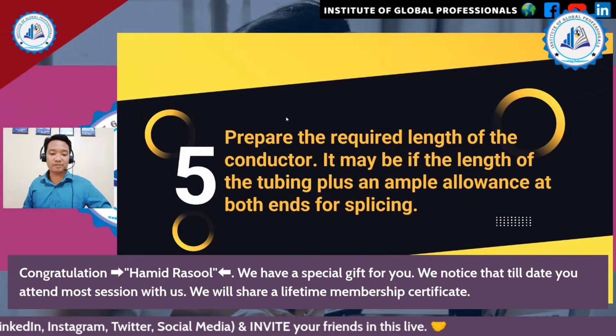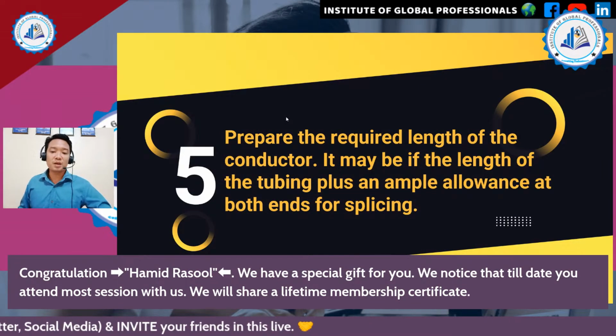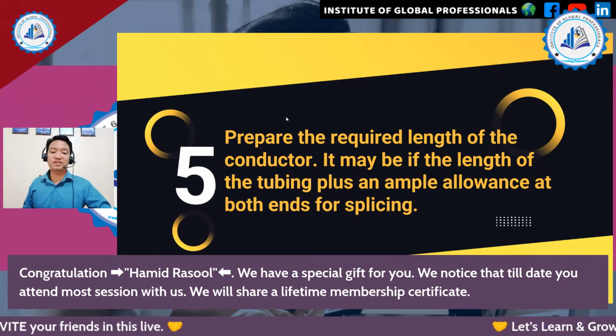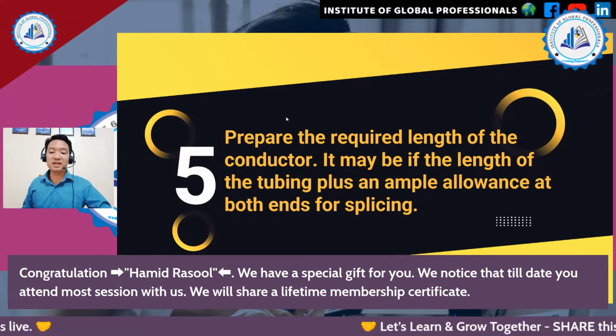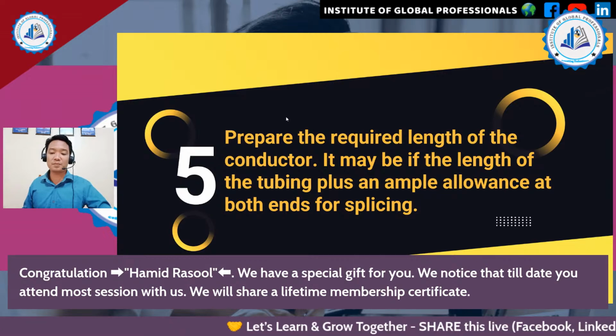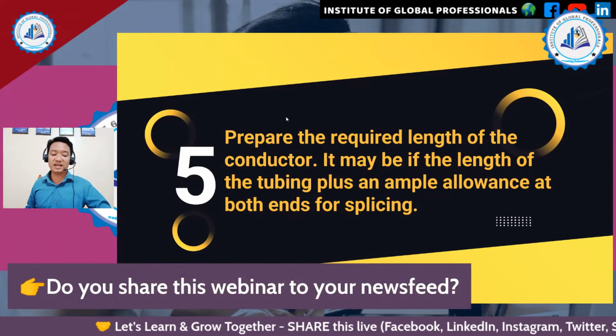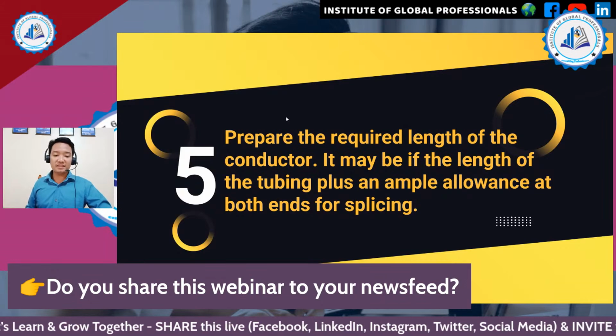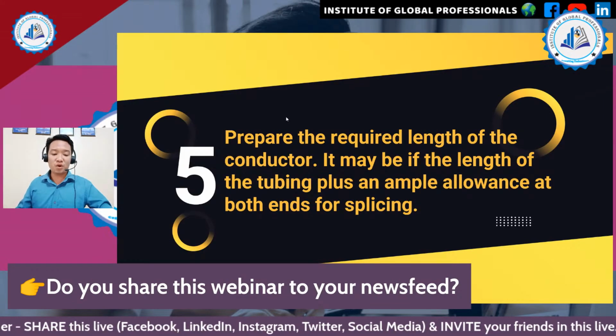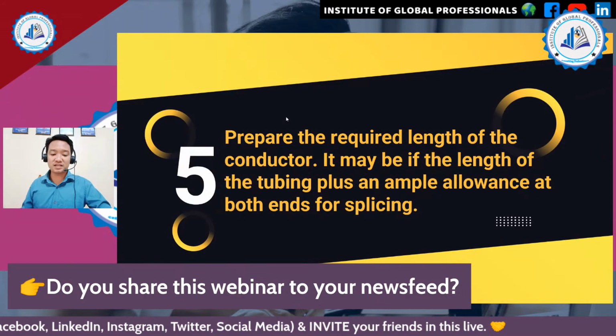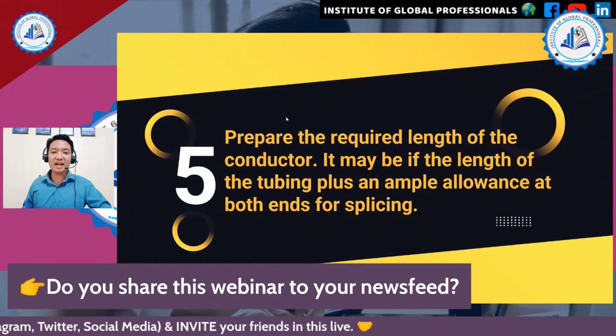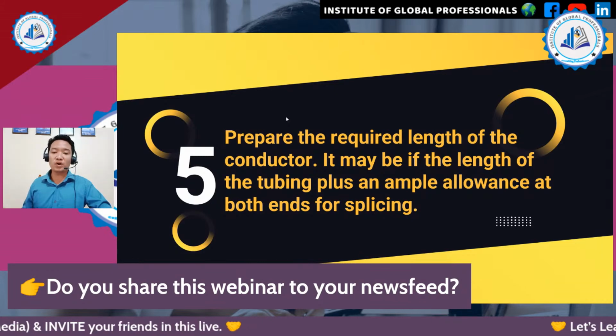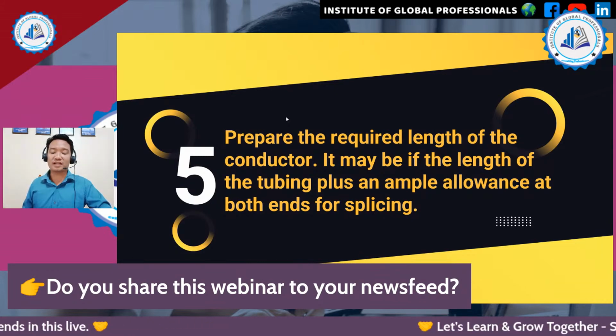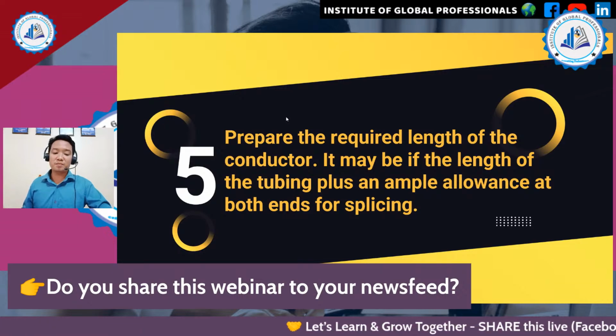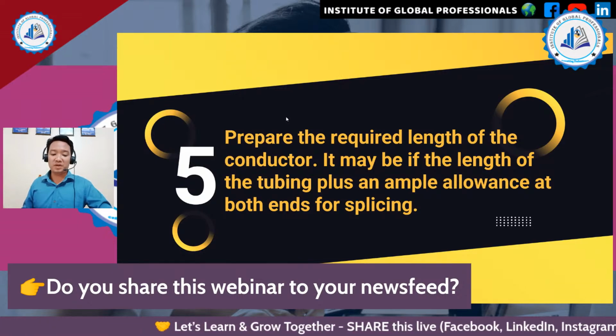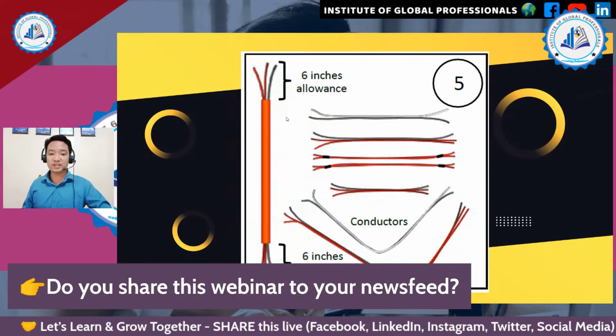And step 5, or the procedure number 5, prepare the required length of the conductor. It may be the length of the tubing plus an ample allowance at both ends for the splicing. And for the splicing, you should always note that the allowance must be at least 150 millimeters, or that is 6 inches long at both ends, and measured from the ends of the tubing. So it should look like this.